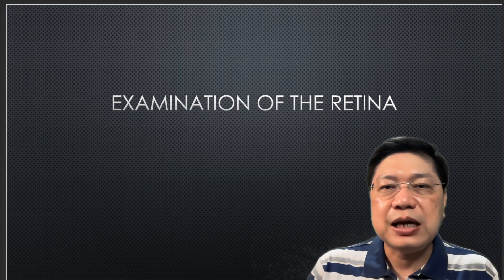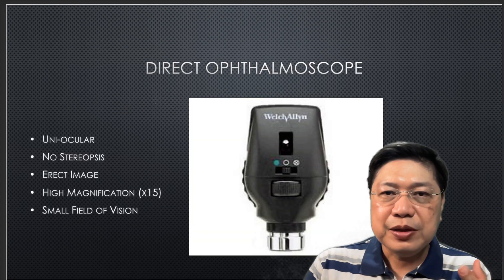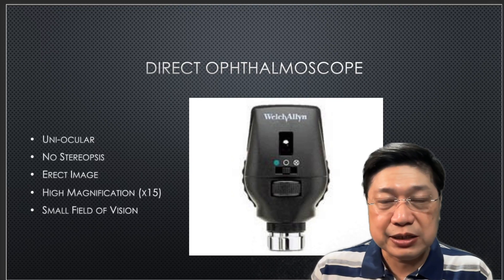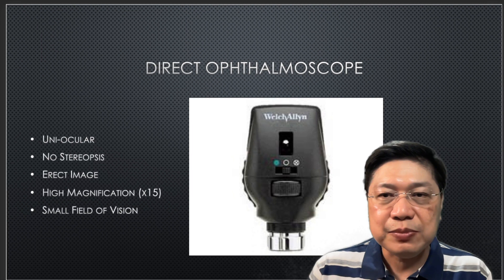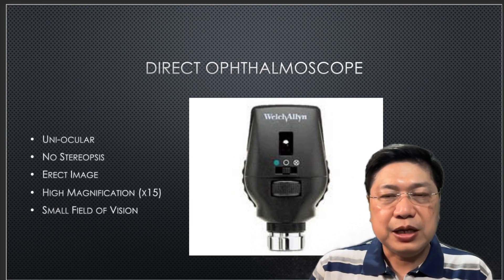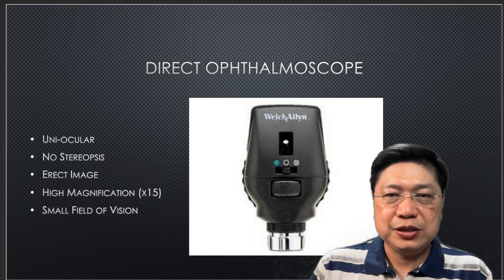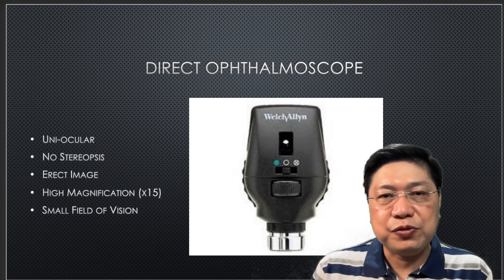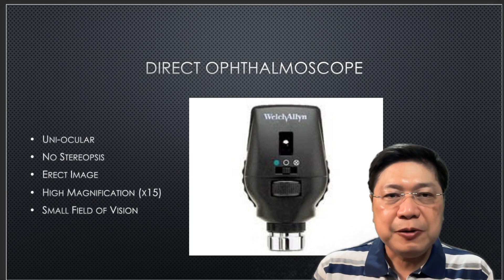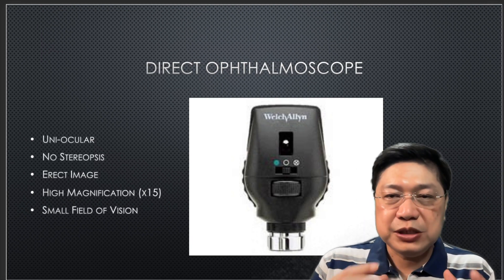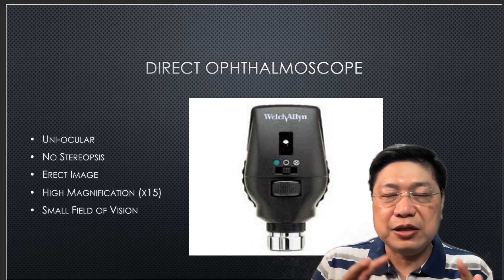So how do you examine something that's at the back of your patient's eye? The most obvious would be using a direct ophthalmoscope, which is uniocular — meaning you can only use one eye at a time — and since you're using just one eye, it doesn't give you stereopsis, meaning you don't see depth. You see something that's flat. It's an erect image — what's on top is at the top and what's at the bottom is at the bottom. It has a high magnification of about 15 times normal, and it has a small field of vision because of that high magnification — so it's a trade-off.